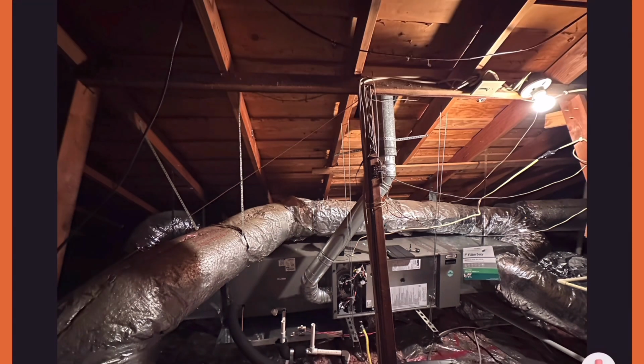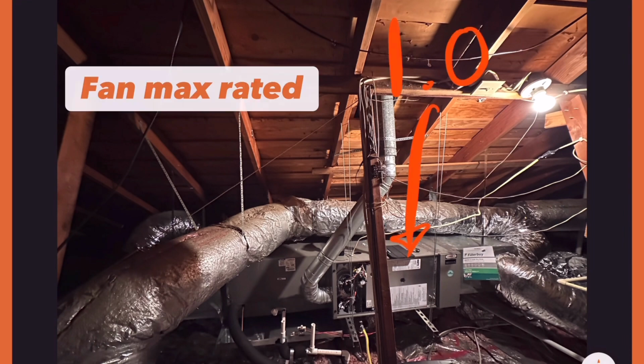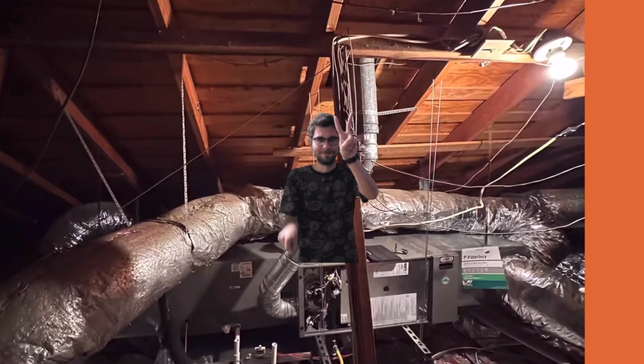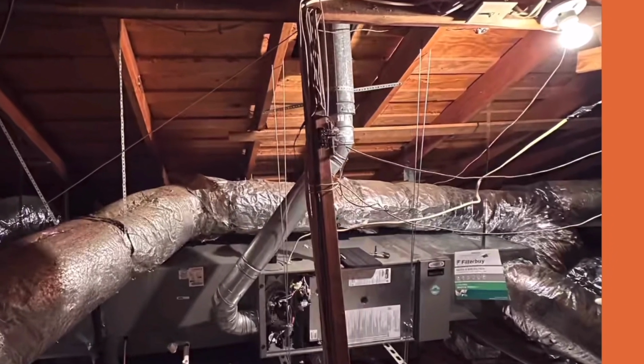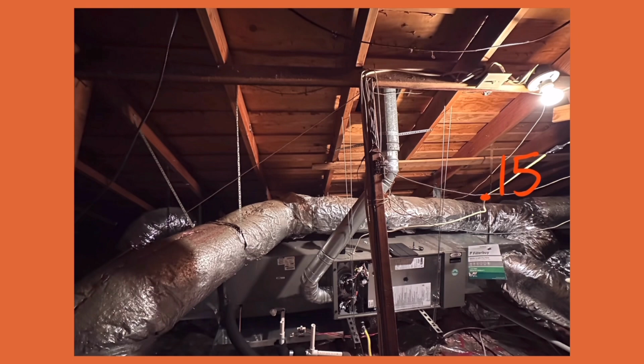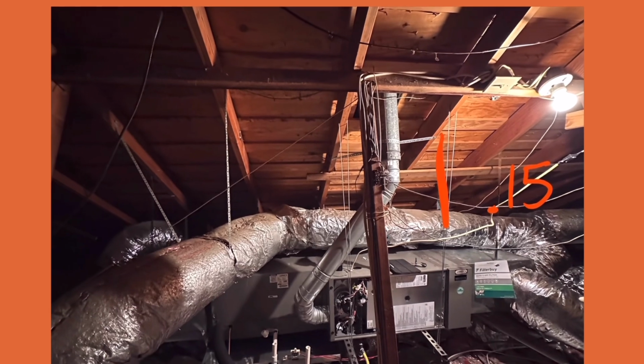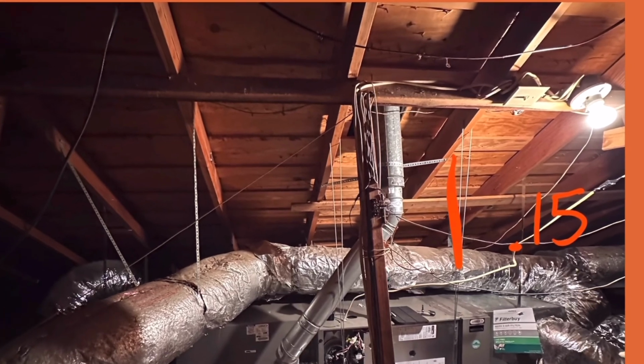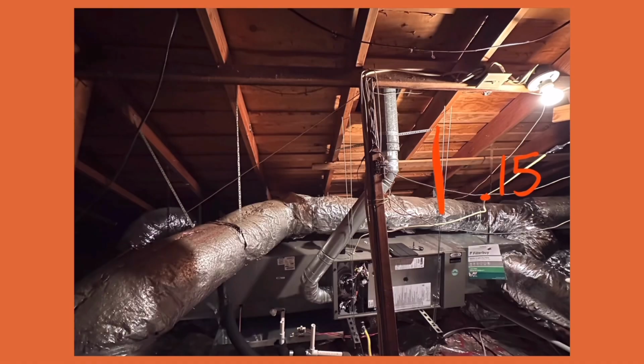All right, so we've got a fan rated at 1 inch of water column maximum. Pretty simple math here: 0.15, so 15% goes to our return duct, 0.15 inches of static pressure on the return side. Your filter gets 0.4. Your furnace has a little bit across the heat exchanger. The coil gets 0.3. And our supply, all the ducts, all the 90s, all the grilles, gets 0.15.